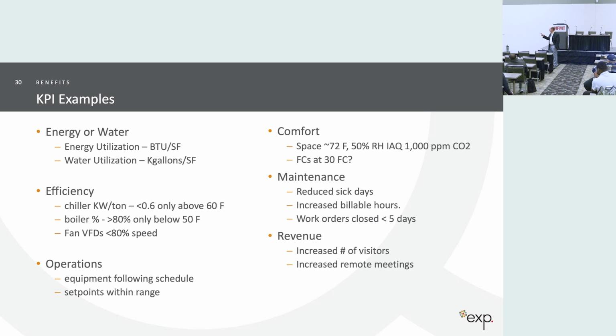Efficiency. Chiller manufacturers know what their kW per ton is, and boiler efficiencies are known too. So have your operators run a contest: how low can you get your kW per ton? Maybe offer a free lunch if someone gets it below 0.5 kW per ton.